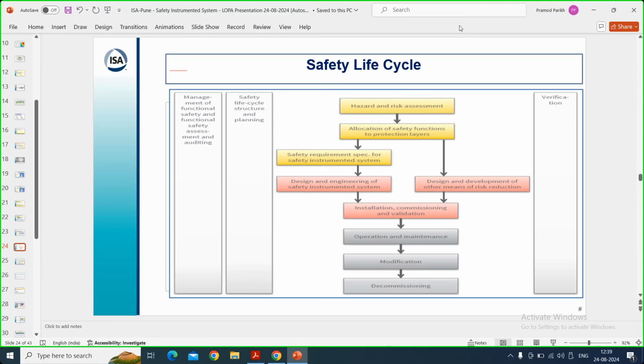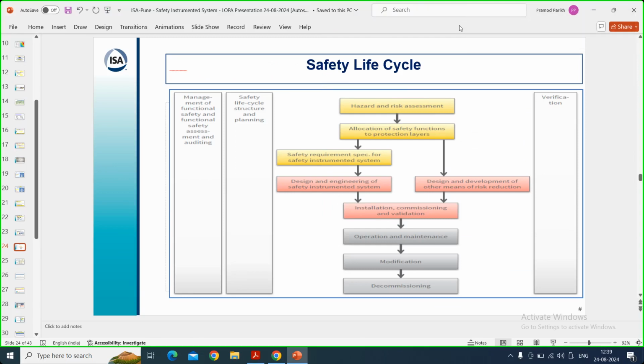So LOPA gives you a much more precise and accurate assessment of the SIL compared to a qualitative selection of SIL by risk graph or risk matrix. Unlike the risk graph and risk matrix, which are more subjective in nature, emotional things can erupt into SIL selection, because it is not very precisely defined. So LOPA is much better. In the USA, people follow LOPA. They don't follow the risk matrix or risk graph. In Europe, they still follow them, but the user has to define the boundaries, and that burden is on the shoulder of the user. In India, we are using the risk matrix more than LOPA.